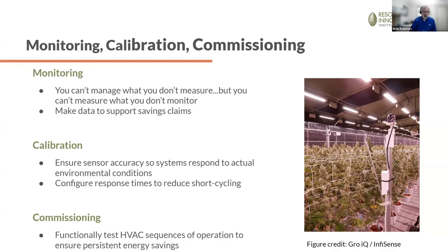Now, the monitoring, you need to decide up front what you need to measure to make you successful, what the key performance indicators are. You have to remember that your sensors have to be calibrated every once in a while, and they have to be in tune with your equipment so that you're not doing something like short cycling.